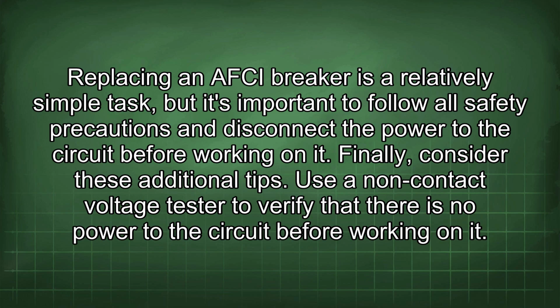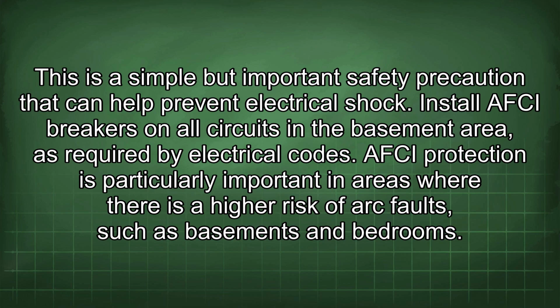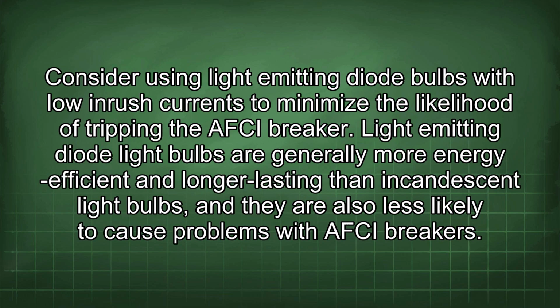Finally, consider these additional tips. Use a non-contact voltage tester to verify that there is no power to the circuit before working on it. This is a simple but important safety precaution that can help prevent electrical shock. Install AFCI breakers on all circuits in the basement area, as required by electrical codes. AFCI protection is particularly important in areas where there is a higher risk of arc faults, such as basements and bedrooms. Consider using light-emitting diode bulbs with low inrush currents to minimize the likelihood of tripping the AFCI breaker. Light-emitting diode light bulbs are generally more energy efficient and longer lasting than incandescent light bulbs, and they are also less likely to cause problems with AFCI breakers.